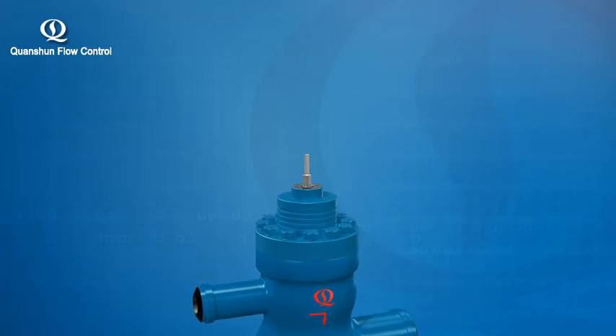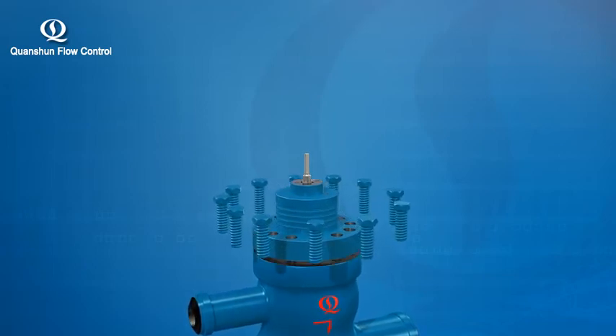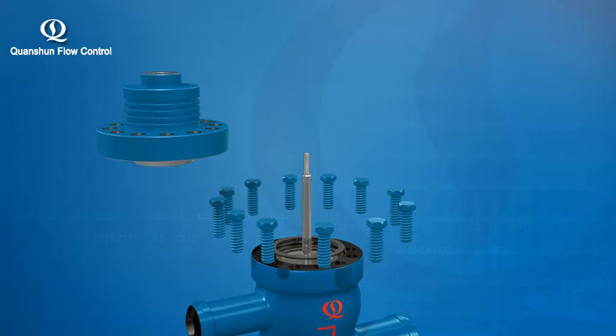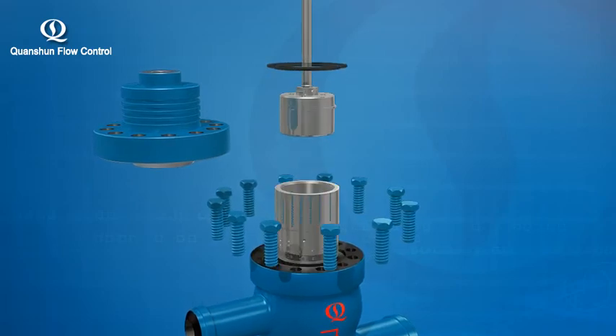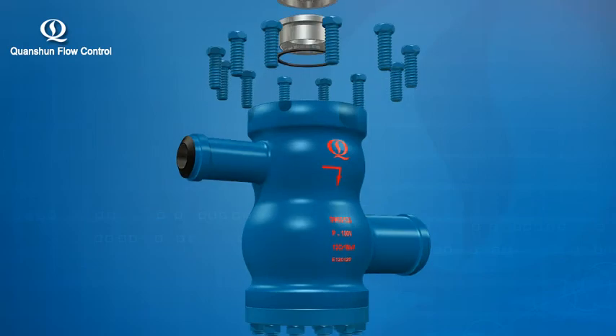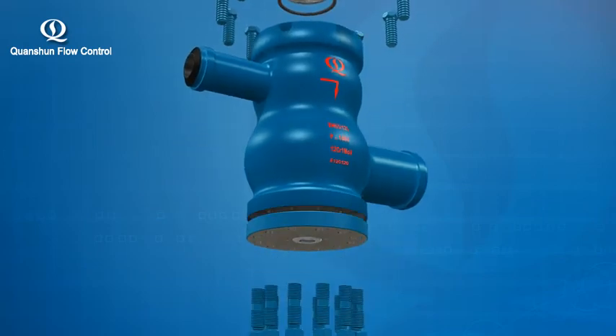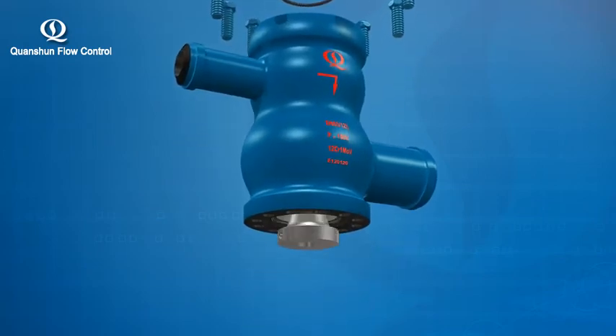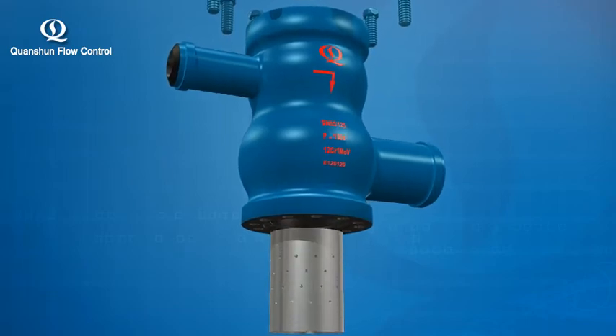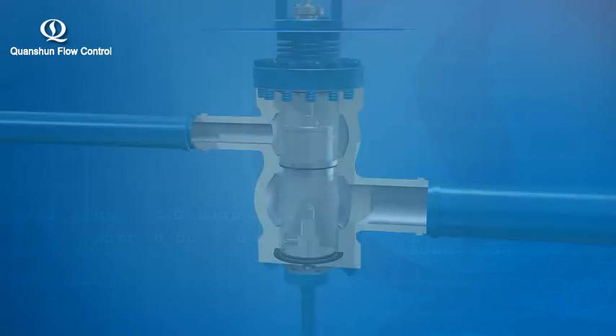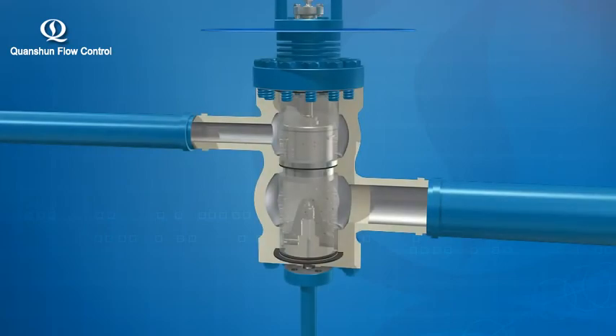2. Water supply system. The water supply system is used to regulate the pressure and check capacity of the temperature reduction water. In order to control the temperature, such task is mainly achieved by the water supply regulator. This regulator has different design differential pressures, and the proper differential pressure to be assumed by the regulator is selected depending on the temperature reduction water pressure PB provided by the user.